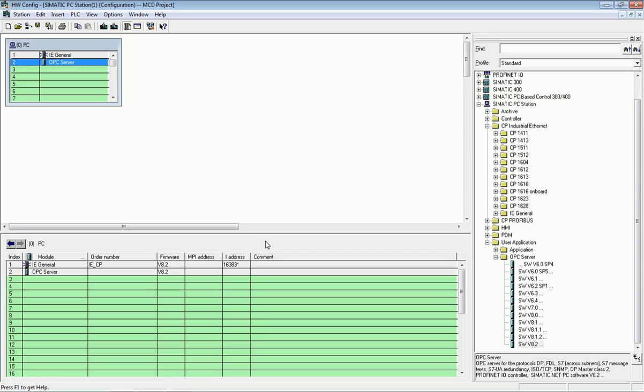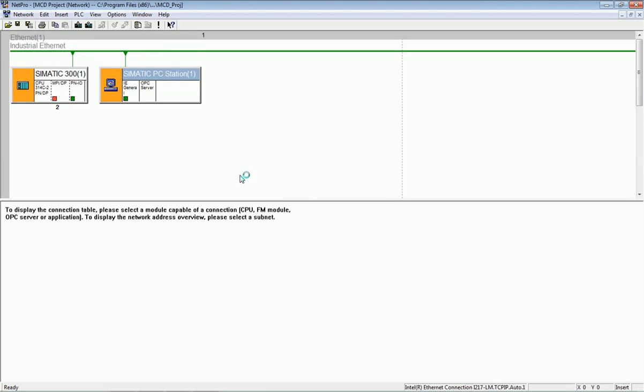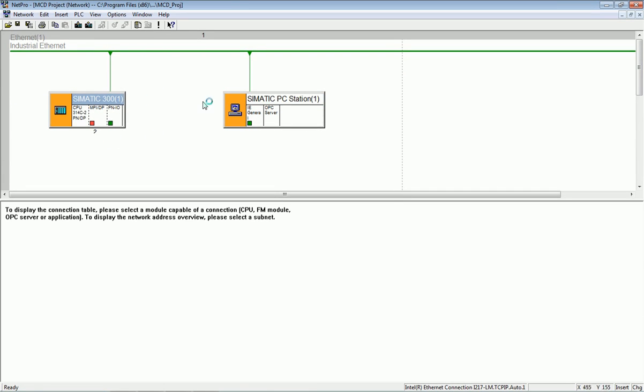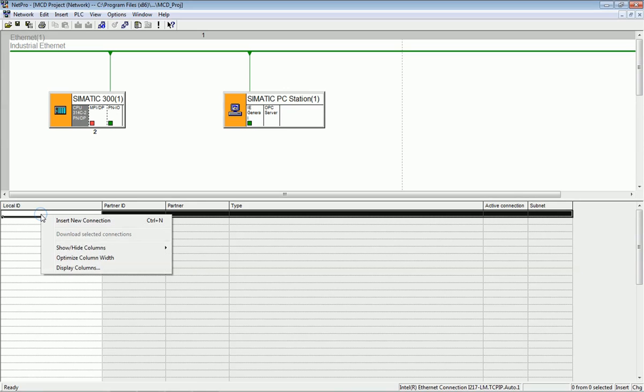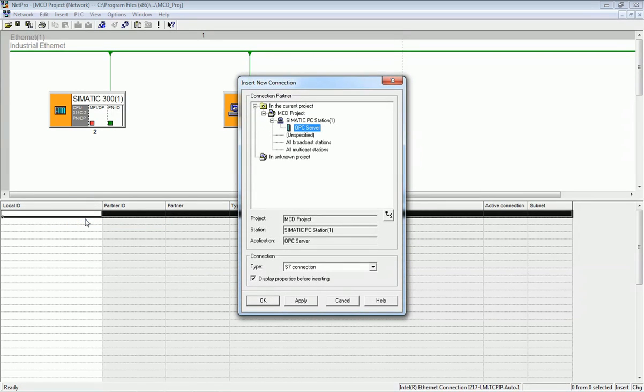After downloading the OPC server into the PC system, we go to the Network View. Here we can see that both the PLC and the Simatic PC station are connected on the same Industrial Ethernet subnet. Now we will establish a connection between the PLC and the OPC. Selecting the PLC, we go to New Connection, select the OPC, and set the connection type to S7 Connection, then press Apply and OK.